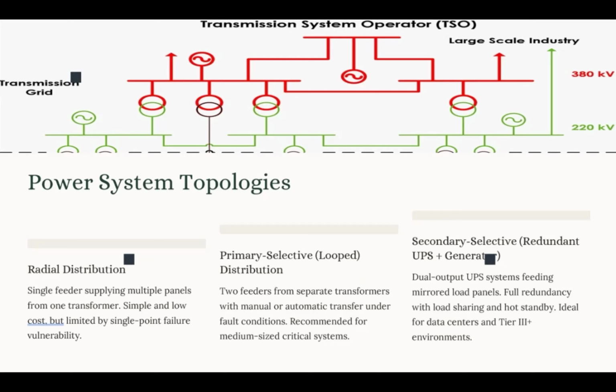Now, if we have a failure upstream on that feeder, that means we lose the entire system. That's the limitation or problem with this topology. But it's significantly cost effective. It's a very cheap implementation, and it's very simple to design because it has fewer components.